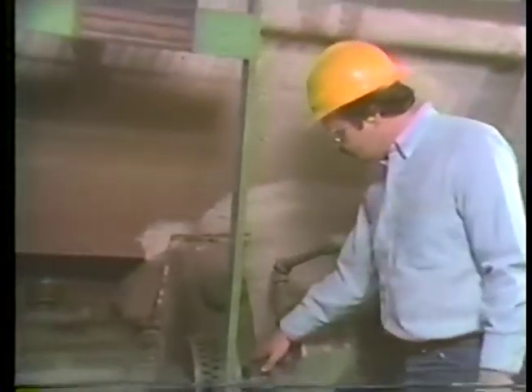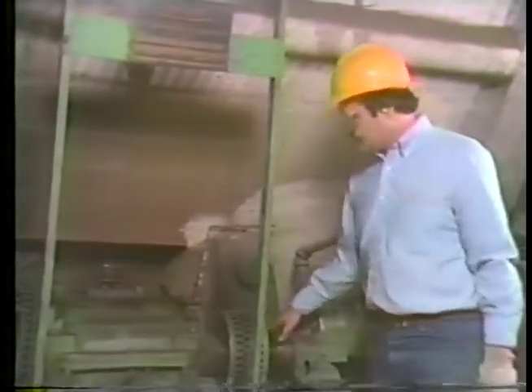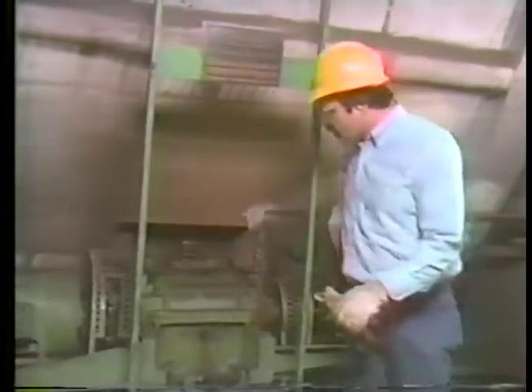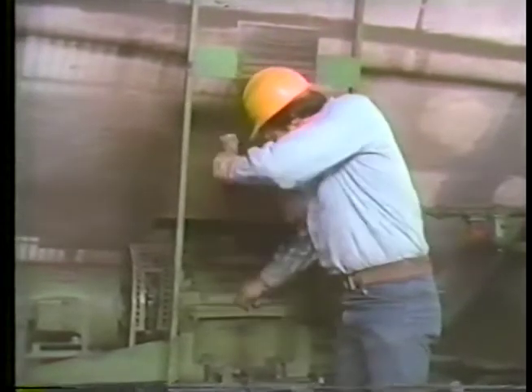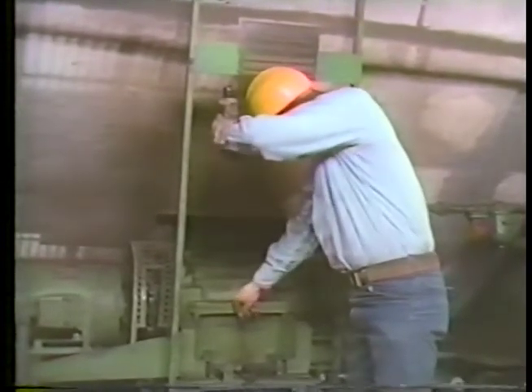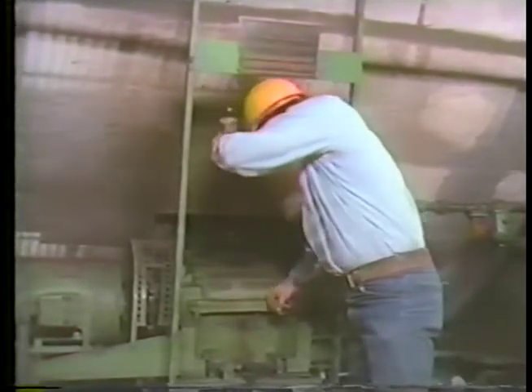Also, during a walkthrough, the operator should check the bearings on all moving equipment needed for startup. Here, the operator is touching each bearing on the motor of the air preheater to check for excessive vibration and temperature. The operator also checks the lubricant level on the bearings to make sure sufficient lubrication is available in accordance with his plant's operating procedures.